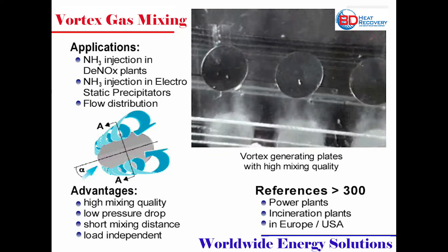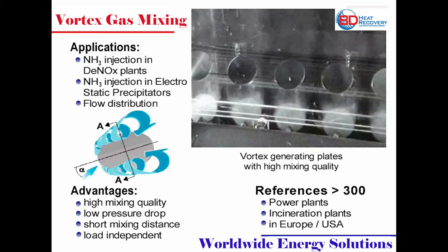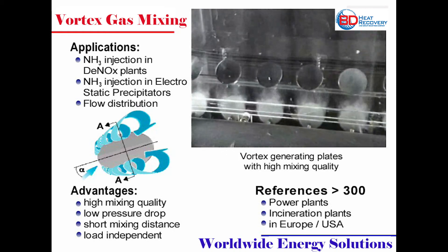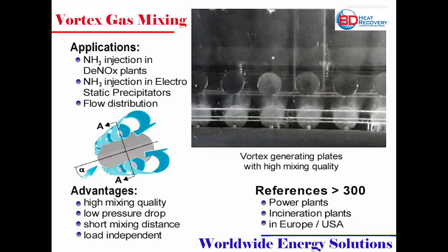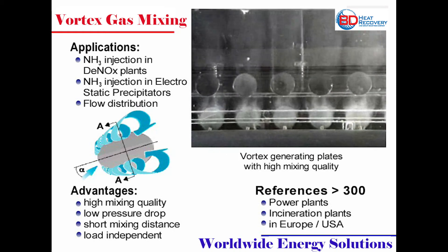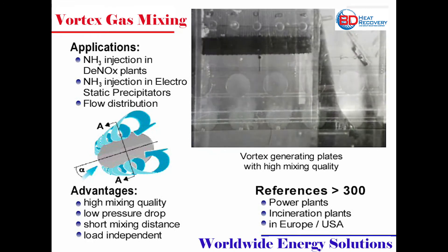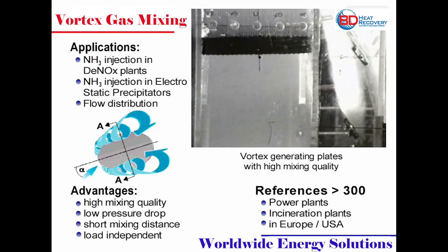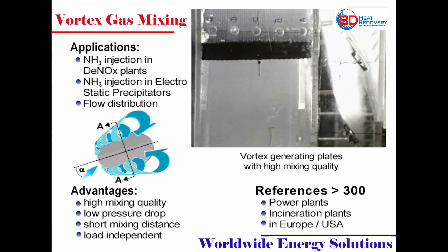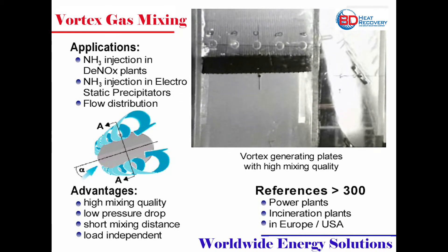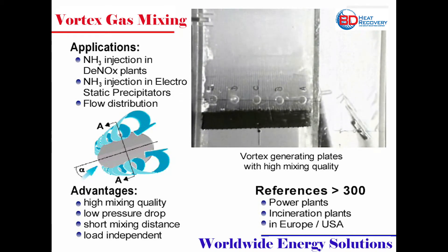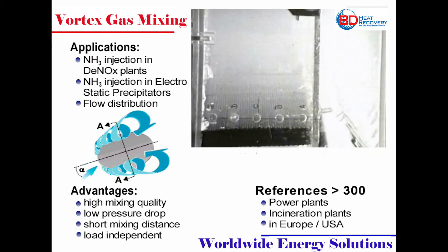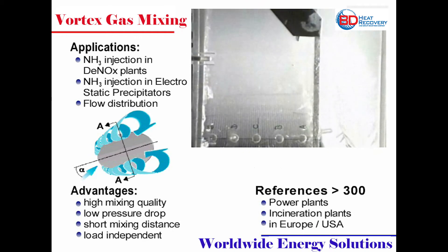The mixer system developed for NH3 injection consists of multiple round discs as shown in the model. The flow rate for the mixture which is injected into the untreated gas can be set at each nozzle. The mixer discs located at the nozzle outlet generate extended vortex with great turbulence directed diagonally to the main direction of the gas flow.